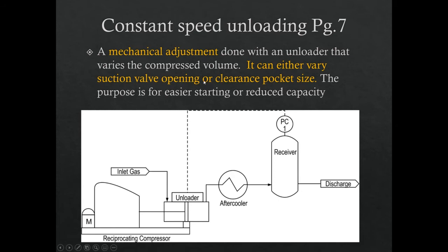Hopefully the next diagram will have a picture of this unloader so I can show you what these components look like. The big idea with this unloader, as the name leads you to believe, is that it takes some of the load off of a compressor when it's starting. I don't know if you've had any experience with it, but with a compressor that's fully charged up and turned off, when you go to start it up again, if there's full pressure on the face of that piston, it takes a lot of effort for that motor to start moving the piston back and forth. So if we can find a way to release the pressure on the face of that piston during startup, it makes starting up a lot easier.